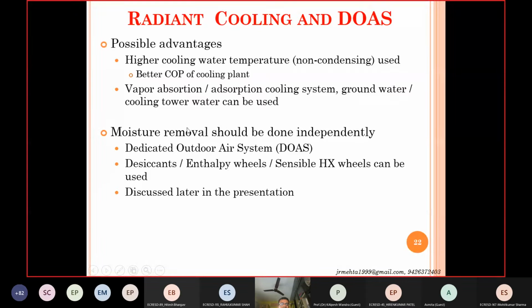And then other options like groundwater or cooling tower water can also be used for cooling in the radiant systems, right? But of course they have a limitation, and generally I have not heard of such a system in a commercial building; these things are done on a trial basis or demonstration building basis. In commercial buildings, they have to generally go for a water chilling plant, but then your chilled water temperature could be higher, so that gives you an advantage on COP.